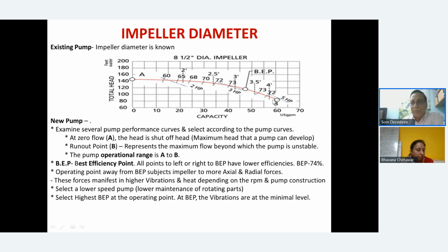Then point B, the runout point. Beyond this, the pump will be unstable in operation. There may be cavitation and issues of this nature. So it is never desired to select a pump where your system curve comes very close to B or very close to A. So select pumps accordingly. Then there is the best efficiency point of the pump, which is, let's say, 74.